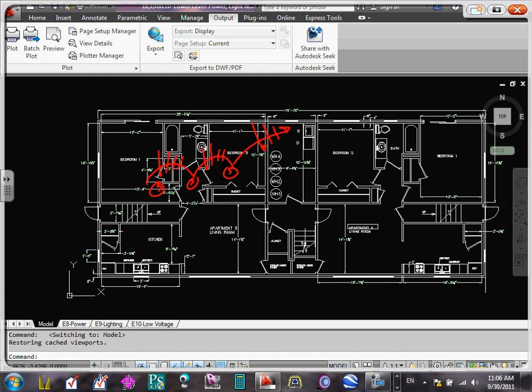Minimum. Okay. The lighting circuits aren't AFCI protected, right? All of them have to be AFCI. Yep. According to the code book, you're not supposed to put fire alarms on that. You're absolutely right. But that's a fire alarm system. A fire alarm system is the 24 volt that we do here at Dunwoody. The smoke detectors that we have at home are not really a fire alarm system. They're power devices. You're right, by fire alarm they mean the full fire alarm control panel, which we're going to be doing next quarter. So they have to be arc fault circuit interrupter protected like every other outlet.